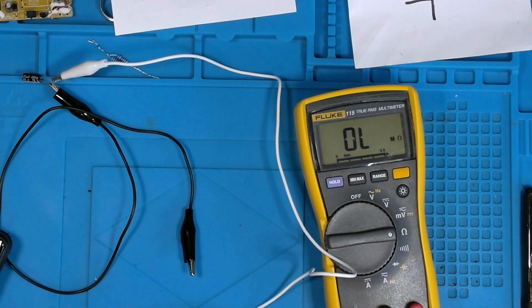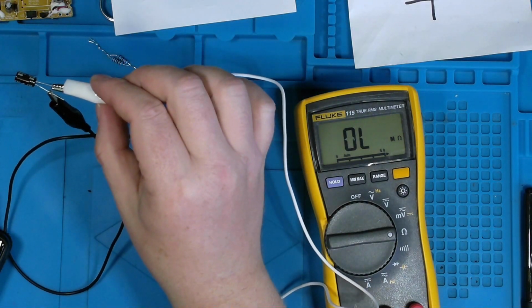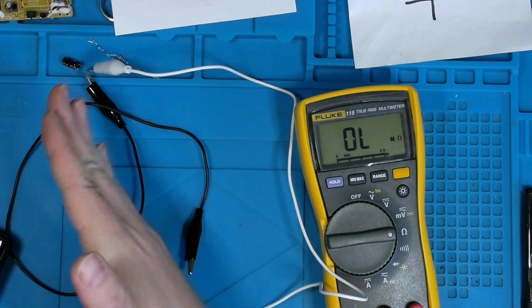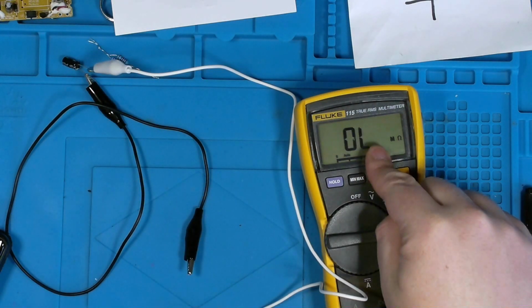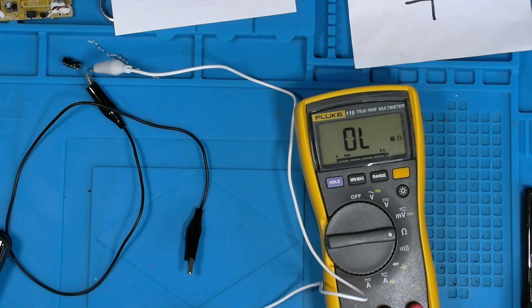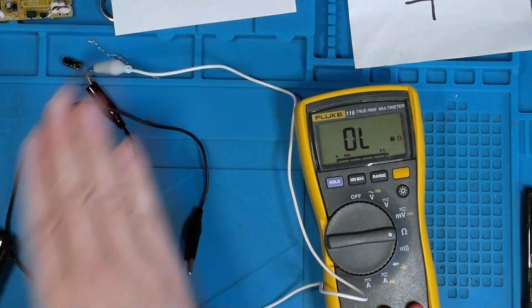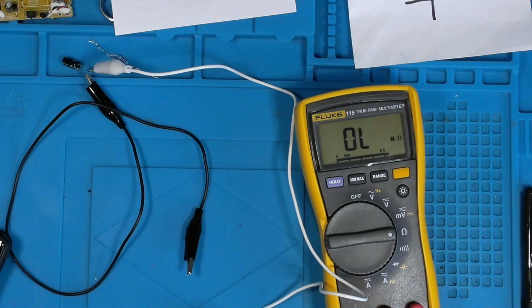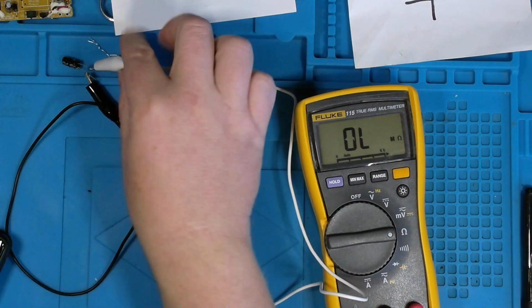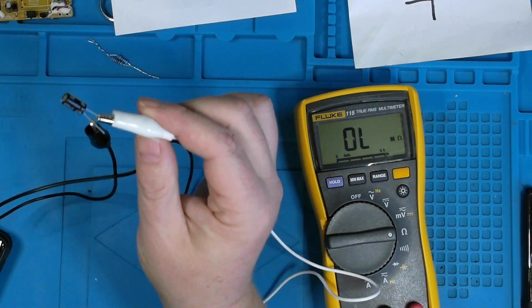That's a good tertiary function for a resistance check, is to see if your capacitors are charging, and if they get to the range of registering OL, or out of range, and then to see if they discharge. But if they measure as a resistor at a constant resistance value, then that capacitor is most likely bad.